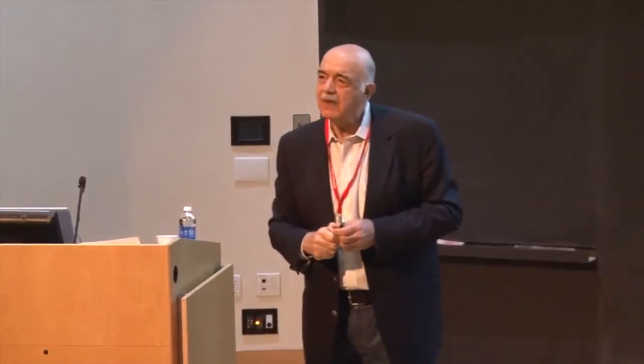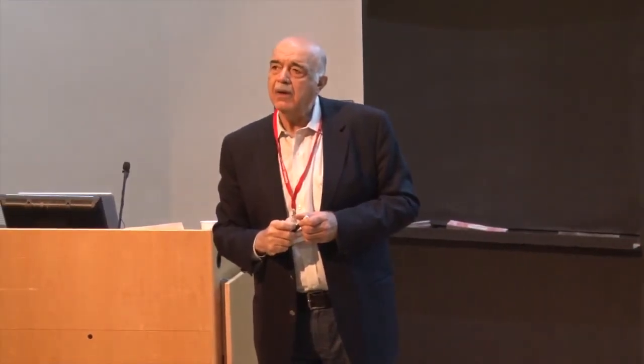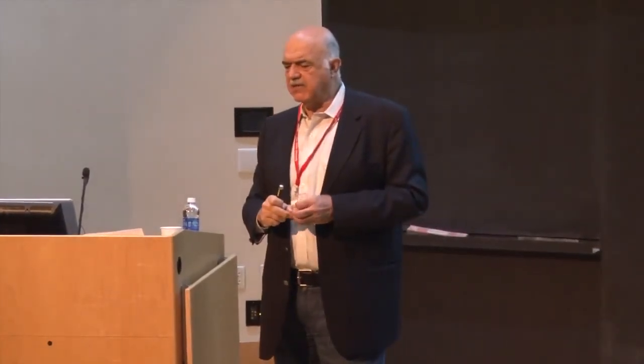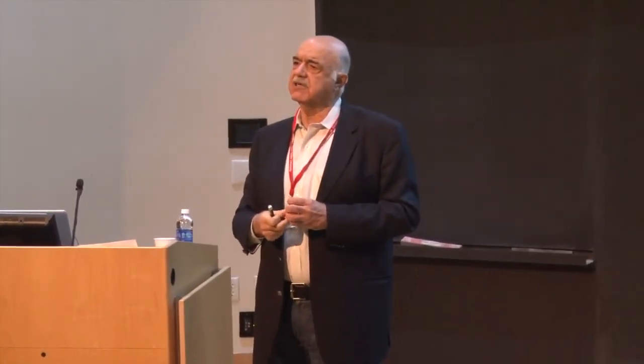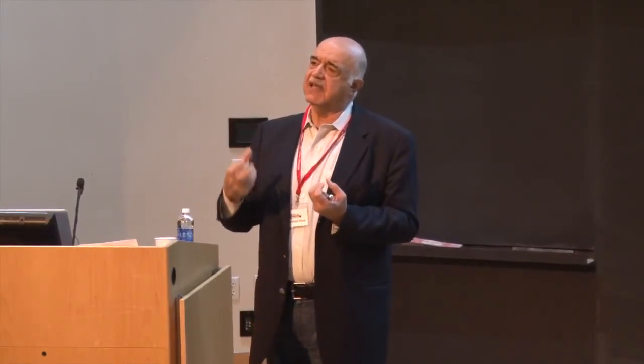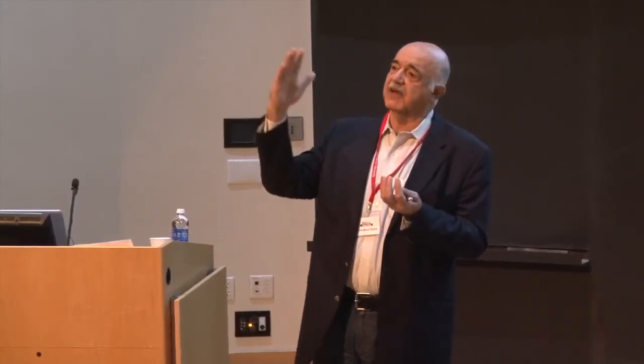Yes? You mentioned the interfacing CMOS to the back end of a common system as a challenge. Right. No, so what I mean by that is that if you look at the 3D imaging systems on the market today, the GE, Siemens, and Philips, they have a handle, like it's my understanding the Siemens has 11 ASICs of their own inside with a number of FPGAs in the handle. And so you have to basically plug your technology into all of their electronics. You can't do it yourself. So you can't buy the system and say, okay, I made a 2D array of Siemens and I'm going to plug it into it, because you need to know what the rest of it is.